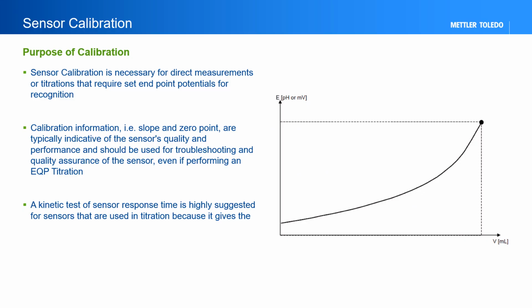Not all titration sensors require calibration. If performing direct concentration measurements, such as pH, or a titration having an endpoint established based off a concentration value, such as a titration to pH 8.3, the sensor used requires calibration.